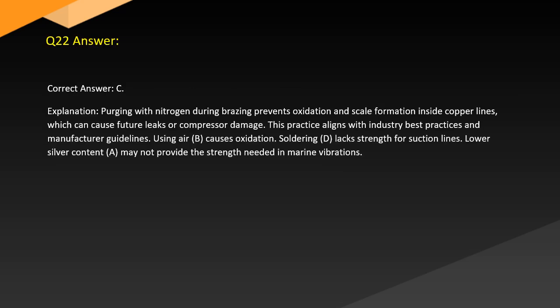Answer. Correct answer: C. Explanation: Purging with nitrogen during brazing prevents oxidation and scale formation inside copper lines, which can cause future leaks or compressor damage. This practice aligns with industry best practices and manufacturer guidelines. Using air (B) causes oxidation. Soldering (D) lacks strength for suction lines. Low silver content (A) may not provide the strength needed in marine vibrations.